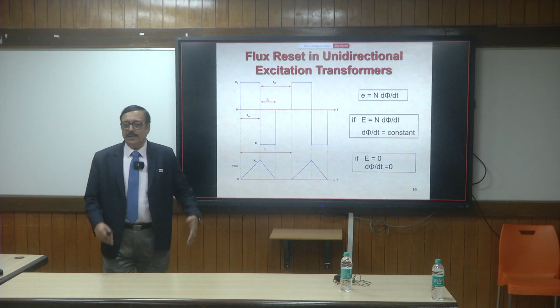Your transformer will fail. So the question is, for how long can this withstand DC? That depends on how long it takes to reach the saturation value, so it depends on the inductance of the transformer, the voltage applied, and the time for which it is applied. This is how unidirectional excitation works in a typical forward converter.